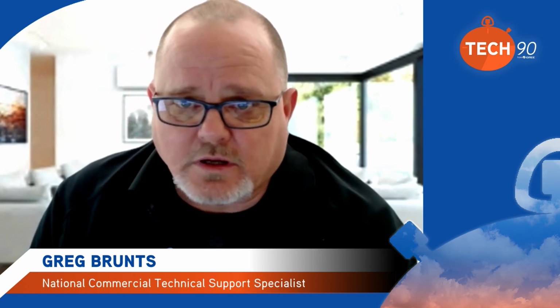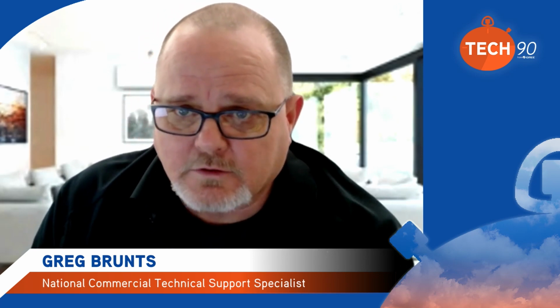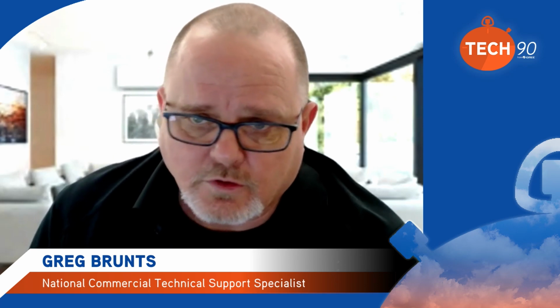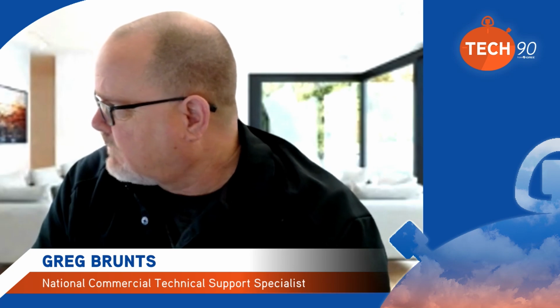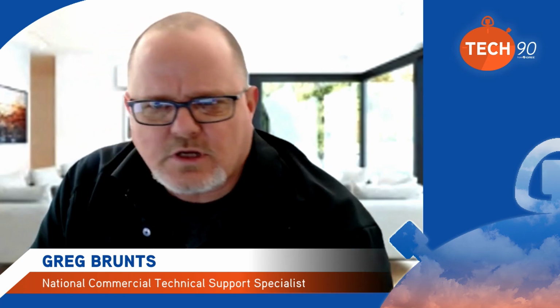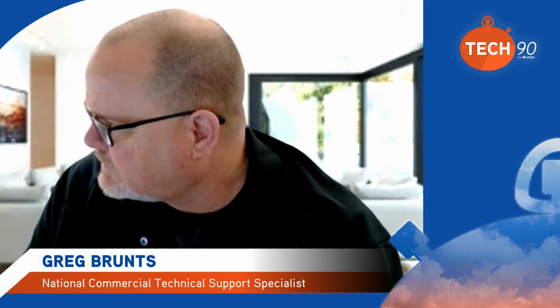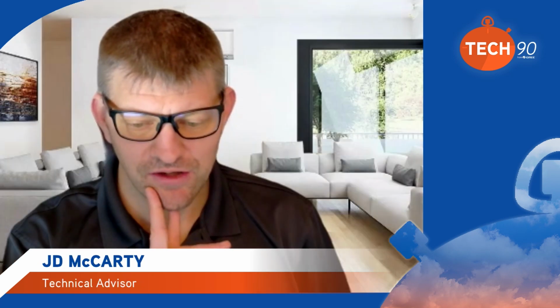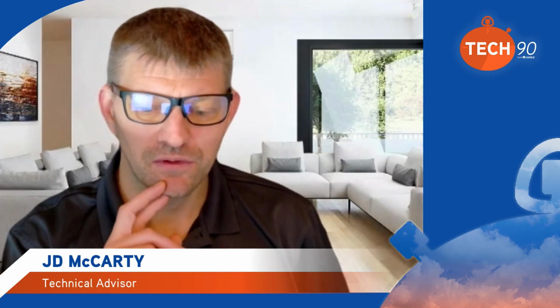As far as recovery machines go, yes, you have to have an A2L rated recovery machine because you are pulling refrigerant out that is considered mildly flammable. As far as vacuum pump goes, I can't imagine why you'd need a special rating on a vacuum pump because you're not supposed to have any refrigerant in there when you're pulling evacuation on a system. So I think that covers most of the tools he mentioned, didn't it, JD? Yep. Yeah, vacuum pump, recovery equipment, and manifold gauges. All right. Yep. Next question.